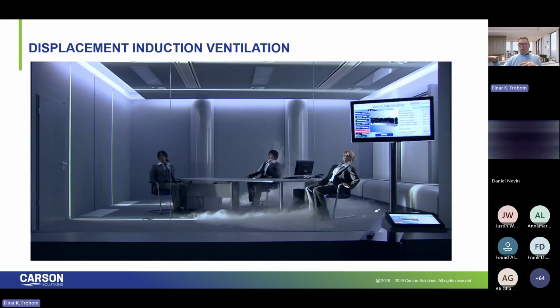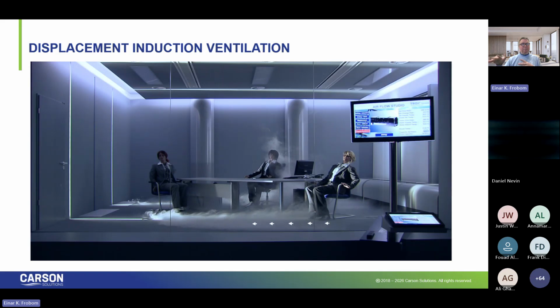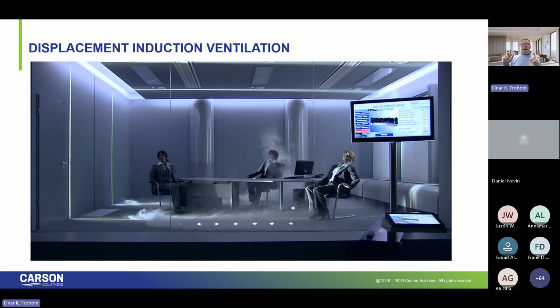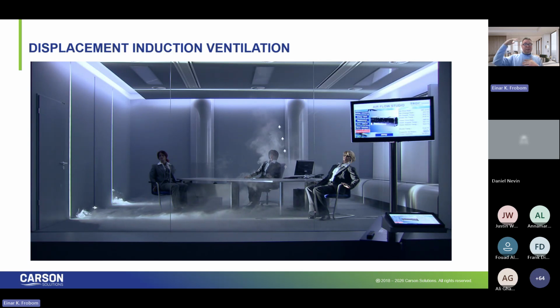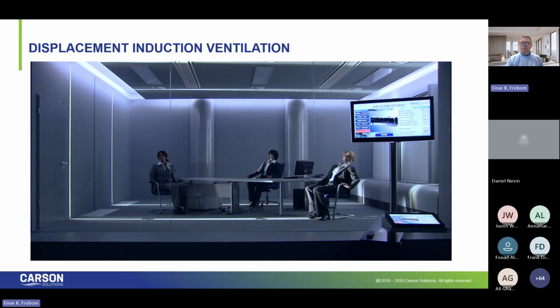There you can see that low, slow velocity, quiet operation of air coming into the space, coming in contact with the heated mannequin, and then delivering that fresh conditioned air up to the breathing zone. But more importantly, those contaminants want to go up. We're just simply going to remove and take away from the other occupants in the space. So that's the general operation of displacement.